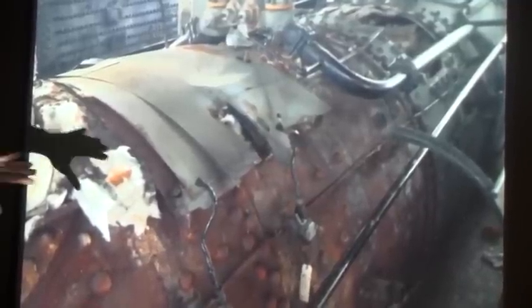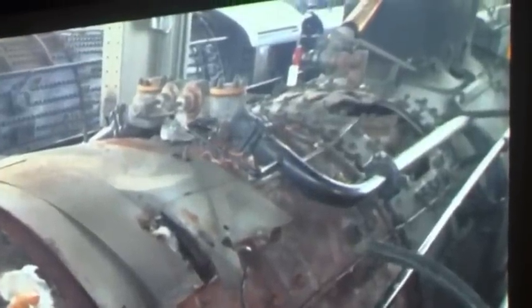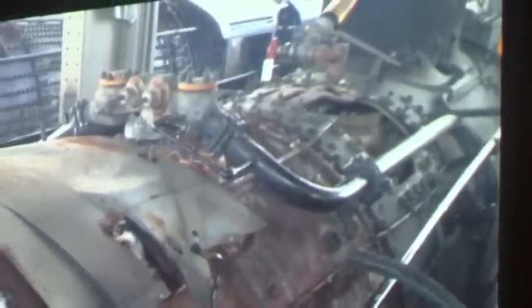There's some parts right here, which is what's left over, some sheet metal that was placed underneath the jacket, and this insulation that really became problematic. With the jacket, the way that it was built, it allowed a lot of water to get in there, and that jacketing, which is a fiber blanket, would retain that moisture. And it was just terrible with that pressure vessel, the outside part of the boiler. Because not being painted, now it can rust.